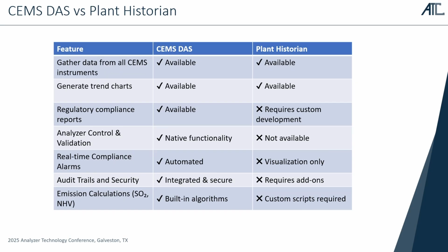So in this table here, I quickly highlight that a data acquisition system and a plant historian both gather all the data from all the instruments. They can generate various trend charts. Now, where it gets interesting is the CEMS DAS would be designed to have all the regulatory compliance reports that are associated with regulation, versus with a historian, you need a bit of custom development.